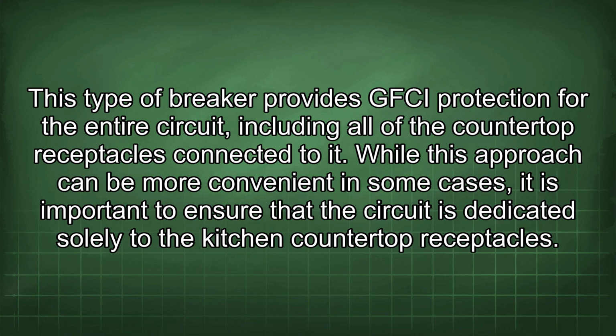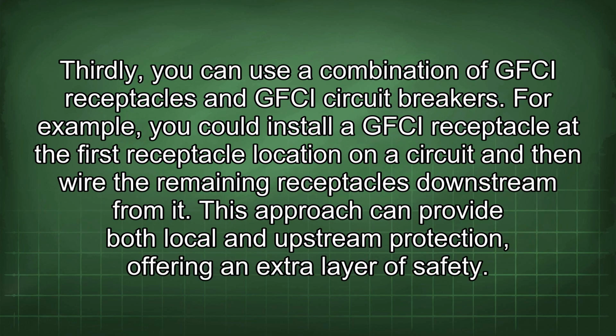While this approach can be more convenient in some cases, it is important to ensure that the circuit is dedicated solely to the kitchen countertop receptacles. Thirdly, you can use a combination of GFCI receptacles and GFCI circuit breakers. For example, you could install a GFCI receptacle at the first receptacle location on a circuit and then wire the remaining receptacles downstream from it. This approach can provide both local and upstream protection, offering an extra layer of safety.